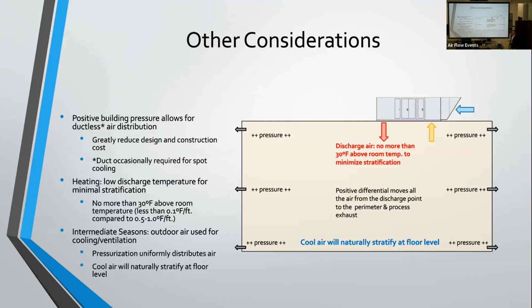Versus if you start to exceed those numbers, I think, Tom, you said it earlier, you'll see typically about a degree per foot of height in the building. Usually makeup air systems that we sell have a higher discharge air temperature than 100 degrees, don't they? I mean, that's not typical, is it? A discharge temperature of 100 degrees? Yes, that's totally typical. Well, 100-degree discharge temperature or temperature rise? No, 100-degree discharge, assuming a 70-degree space. Okay, yeah, so pretty typical.